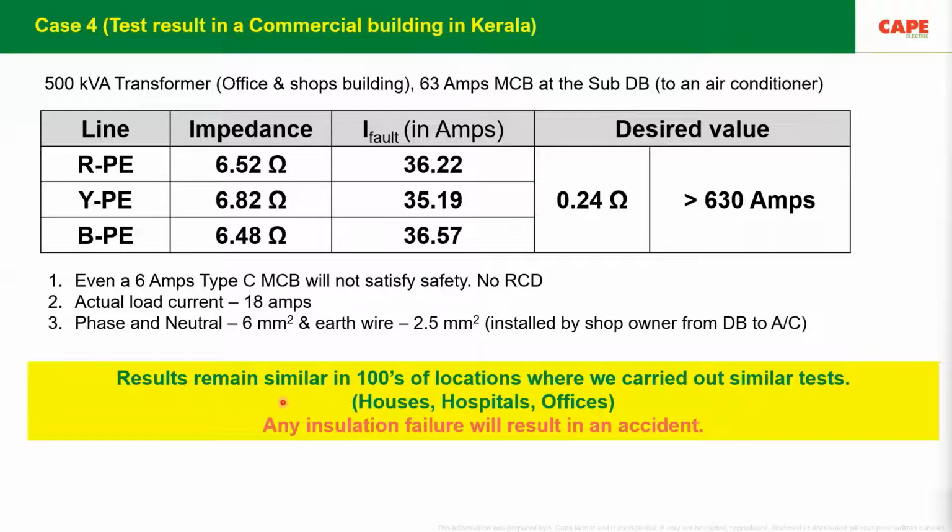Similar results to this shop are remaining in hundreds of locations across India. I would say more than 90 to 92% of our installations have similar earth fault protective measures, which means there is no safety at all. It is common in houses, hospitals, and offices. Any insulation failure will result in an accident.